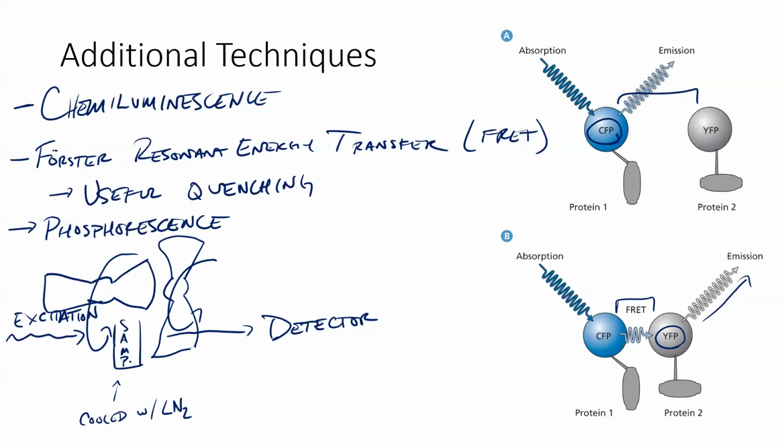And so I'm going to use my hands as these shutters. And so the sample is down here at the bottom. Light comes into the sample and it excites whatever's in there. And as these turn, this one cuts off the light, and so it can fluoresce a little bit. And this one opens it up so that after fluorescence is done, only phosphorescence reaches the detector. And then it goes in a circle, but my hands don't. So that light can hit the sample again, excite it. We do our fluorescence while it's dark, and then only phosphorescence reaches the detector.